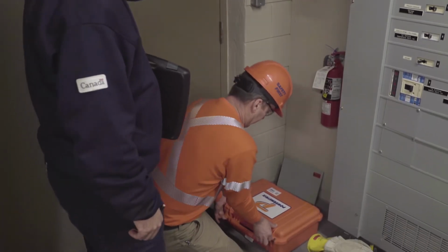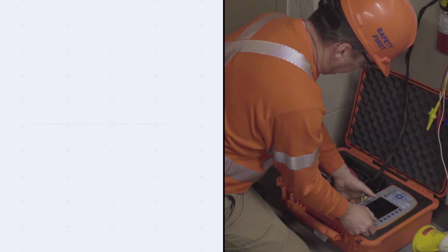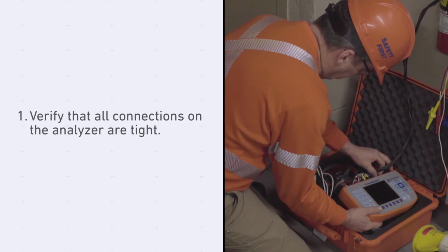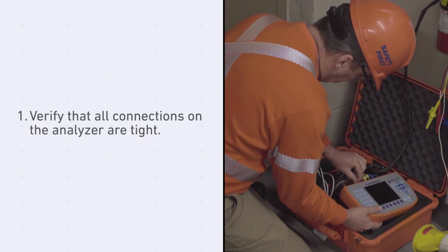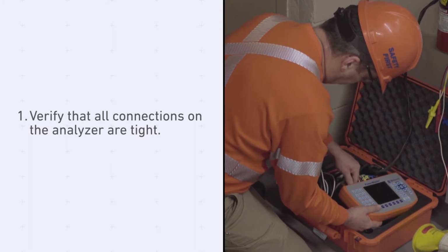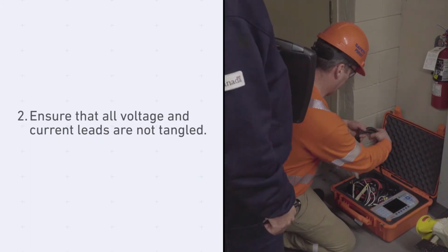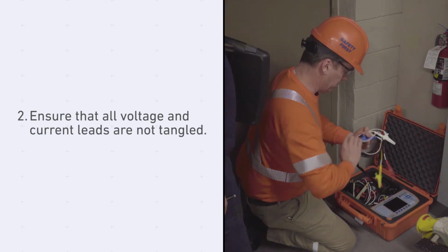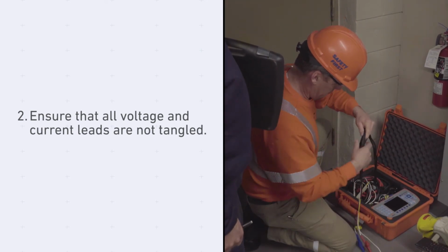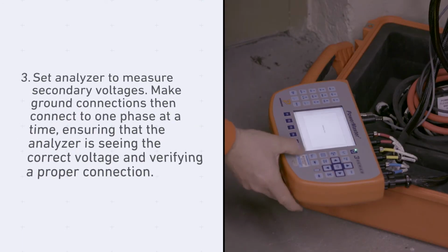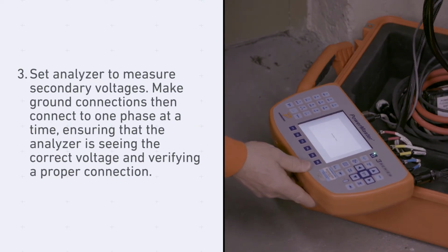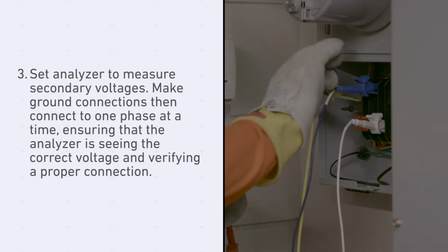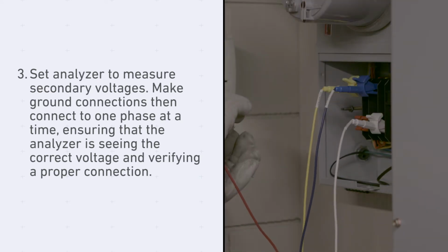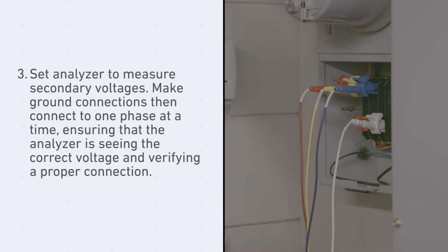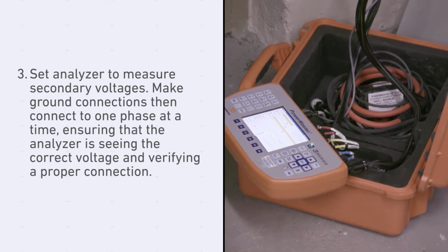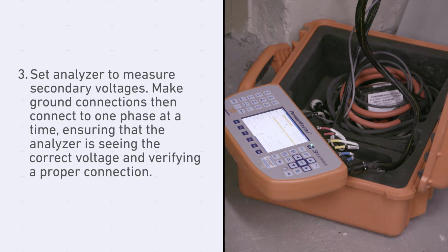Follow these steps to connect the analyzer in a safe manner. 1. Verify that all connections on the analyzer are tight and have not been damaged during transportation of the device. 2. Ensure that all voltage and current leads are not tangled together in such a manner that may cause safety concerns. 3. With the analyzer turned on, set it to measure secondary voltages. Make ground connections first, then connect to one phase at a time, ensuring that the analyzer is seeing the correct voltage and verifying a proper connection.